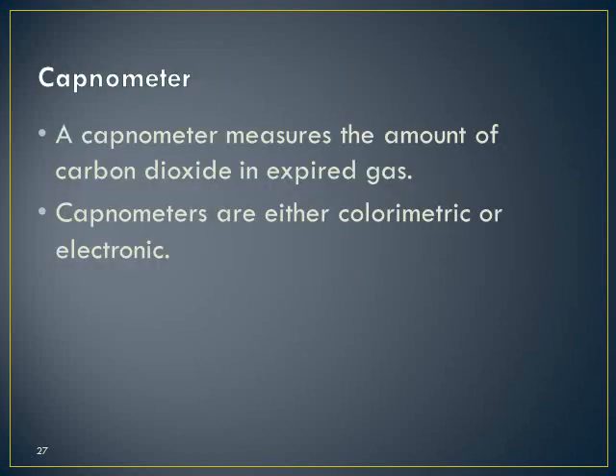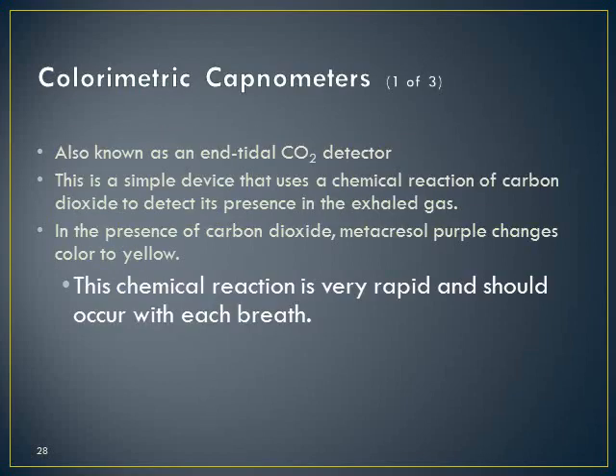So a capnometer is a device that measures the amount of carbon dioxide in expired gas. Capnometers are either colorimetric or electronic. Most of the time we have a combination of both nowadays. If you have colorimetric, it's usually best to pull those out right at the beginning and verify them. Basically, they work off the principle of a litmus paper. We'll talk about those in the next slide here. But they are End-Tidal CO2 detectors.